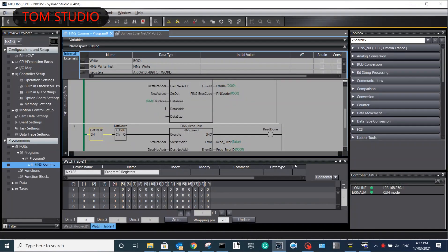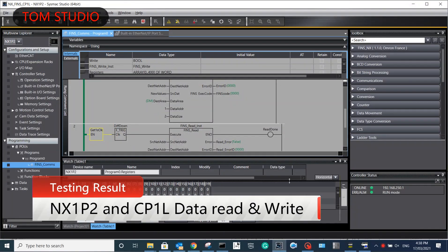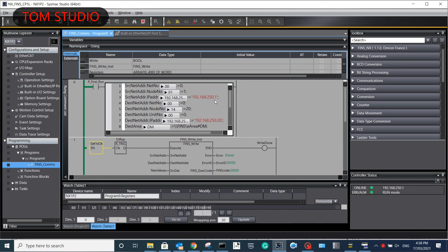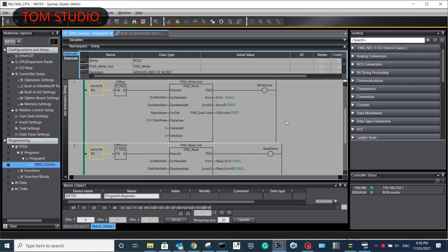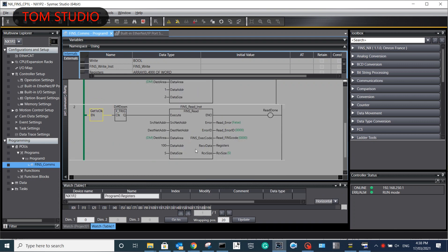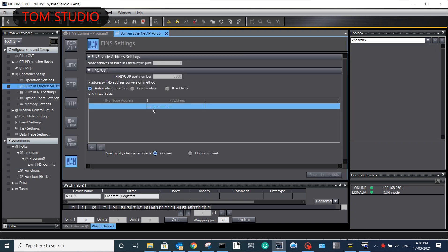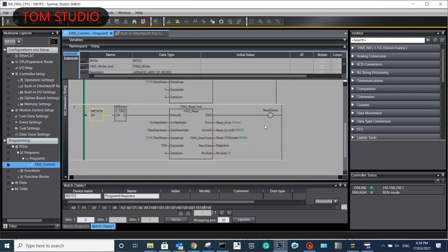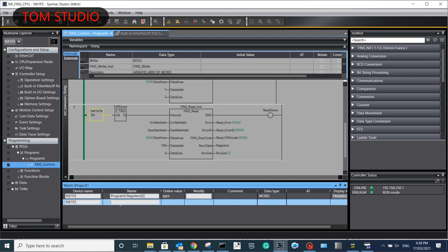In the last step, we test the communications between NX1P2 and CP1L. The NX1P2 IP address is 192.168.250.1, and the CP1L IP address is 192.168.250.100. Sending data from NX1P2 to CP1L will be located at the D memory area, starting from D1. Received data from CP1L to NX1P2 will be located in a register data array from array word, so we can read the values from CP1L PLC freely.